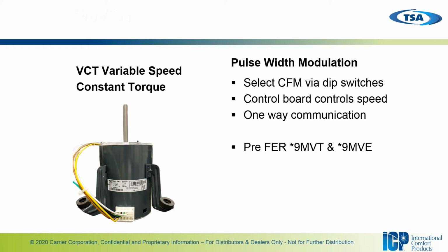And now let's talk about the variable constant torque motor. This is a motor that receives a pulse width modulation signal. For those of you that don't know what pulse width modulation is, it is a voltage pulse. This pulse typically happens so quickly that a multimeter is not capable of picking it up. Therefore, the meter typically averages the voltage out.